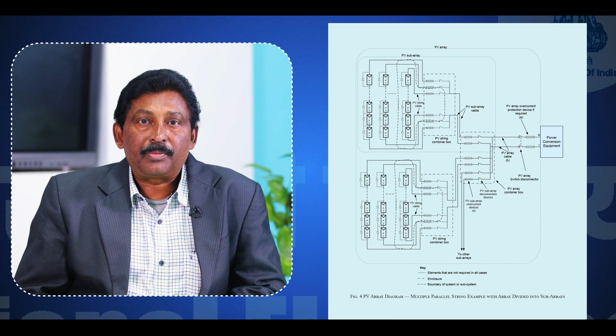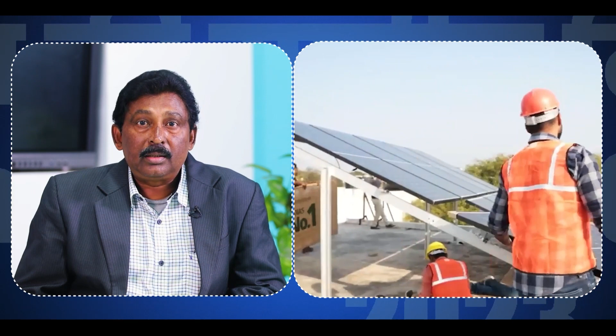Special cable requirements for DC side, IS 17293, and for AC side like FRLSH cable are also provided. Guidance for design of the system with selection of components and their specific requirements have been included. While preparing this part, effort has been made to align the requirements as far as possible with the corresponding IEC standard IEC 60364-7-712, updating it with Indian experience. As a result, some changes have been made to cater to the need, keeping in view the typical Indian environment condition prevailing and safety requirements required to be met as per IS 732.